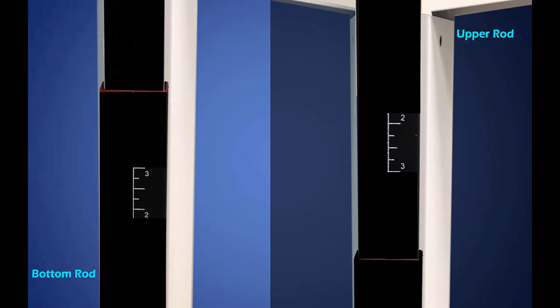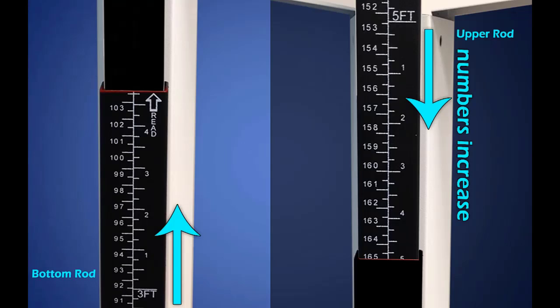On the bottom bar in the left image, the fractional line that represents the 2 1/4 inch mark is here. The 2 1/2 inch mark is here, and the 2 3/4 inch mark is here. Now on the upper bar in the right image, the fractional line that represents the 2 1/4 inch mark is here, the 2 1/2 inch mark is here, and the 2 3/4 inch mark is here. Remember, the bottom rod numbers increase from bottom to top. The upper rod numbers increase from top to bottom. The simplest way to interpret the calibration markings correctly is to observe the direction that the whole numbers are increasing. Then you will be able to interpret the fractional markings correctly.